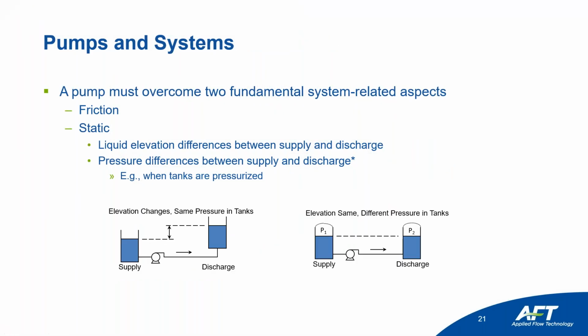So here we're going to start talking about pump and system curves. Pumps and systems need to overcome two fundamental aspects. They have to overcome friction, so that's your standard frictional losses in a pipe, and static head. Static head is your liquid elevation differences from your reservoirs. Or if you have pressurized tanks, your liquid heights could be the same, but then your static head is going to be based upon the pressure differences in that case.